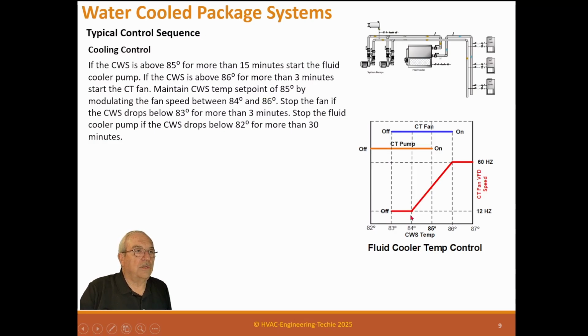Cooling control. If the condenser water temperature is above 85 degrees for more than 15 minutes, start the fluid cooler pump. If the condenser water is above 86 for more than 3 minutes, start the cooling tower fan. Maintain the condenser water temperature set point of 85 degrees by modulating the fan speed between 84 and 86 degrees. Stop the fan if the condenser water drops below 83 degrees for more than 3 minutes. Stop the fluid cooler pump if the condenser water drops below 82 degrees for more than 30 minutes.